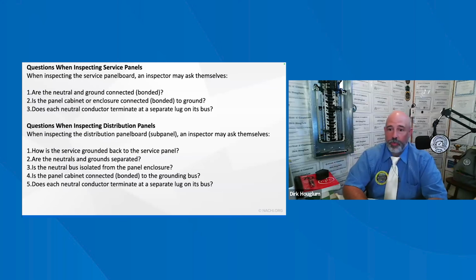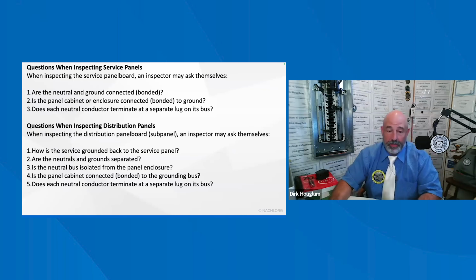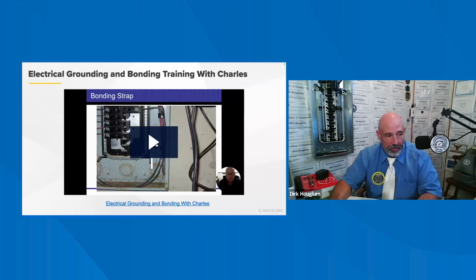250.32(B)(1). It is also important to understand that if the detached structure is being fed by a single branch circuit and it contains an equipment grounding conductor that is used for grounding non-current carrying metal parts or equipment, then no grounding electrode system is required. The inspector should pay very close attention to the grounding and bonding of all electrical circuits. Sometimes it is very hard to figure out which components are electrically connected to each other. When in doubt, I always recommend a licensed electrician for further evaluation. Always a good idea. Okay, we are going to watch this video.